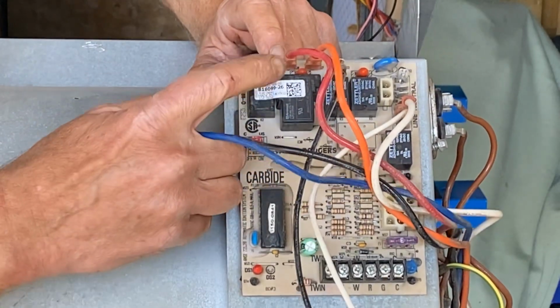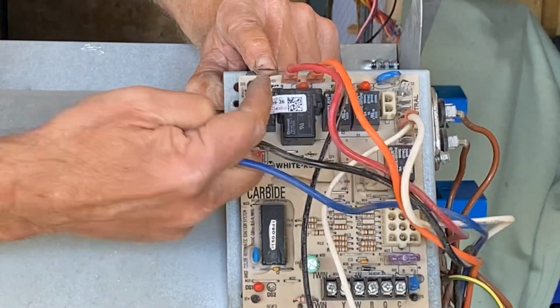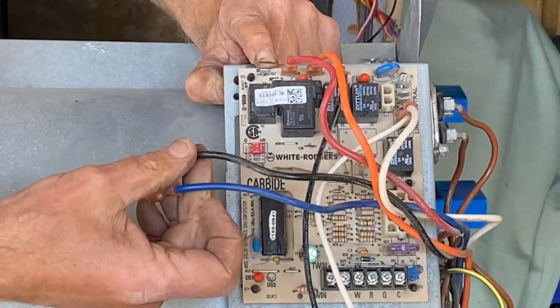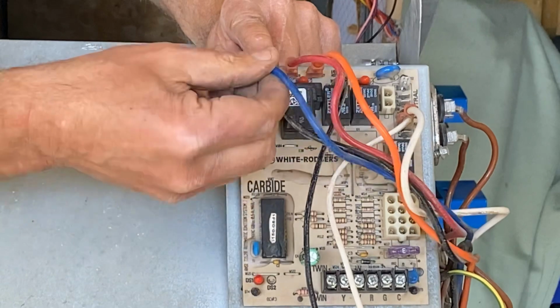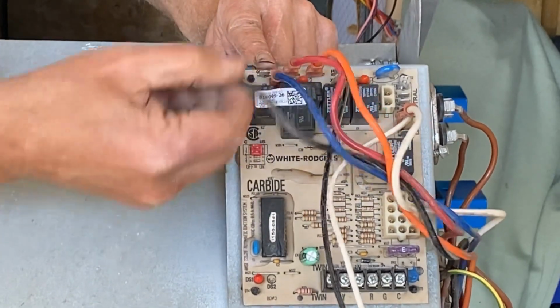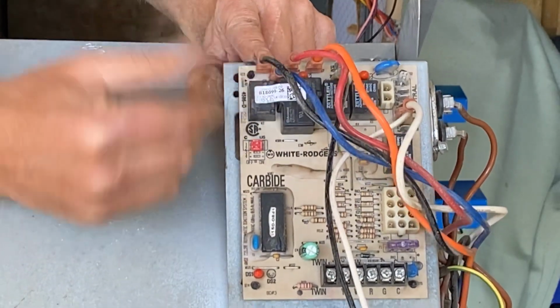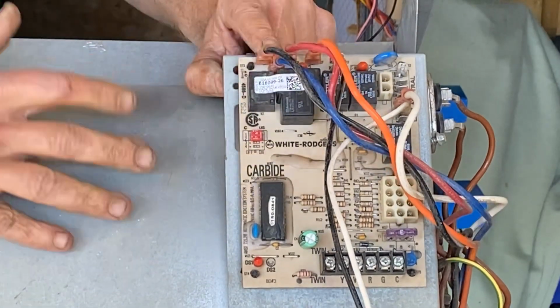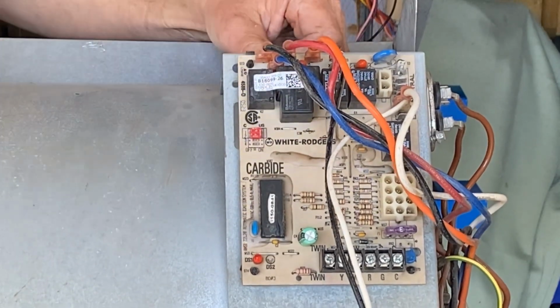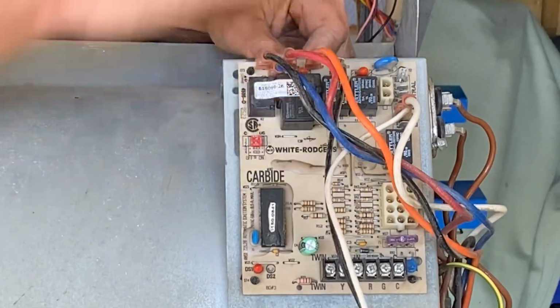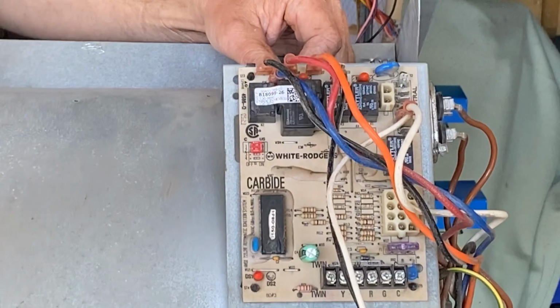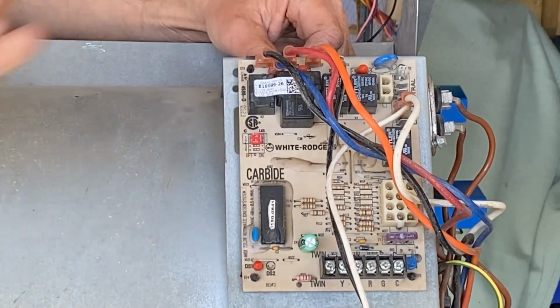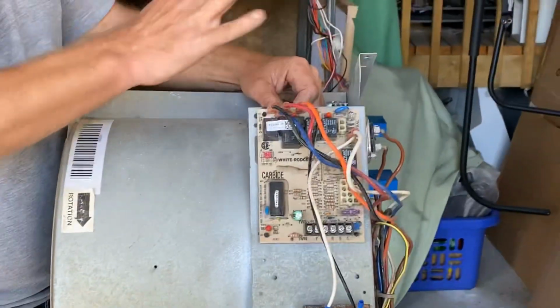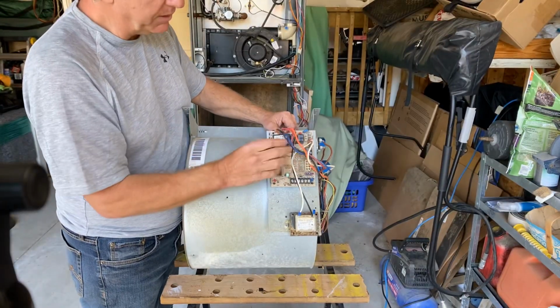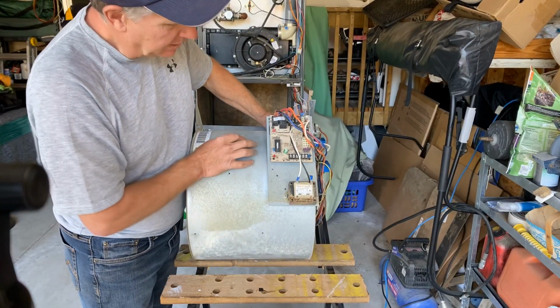Then I've got a terminal that says cool, and a terminal that says heat. I'm going to put the low speed on heat, and the high speed on cool. So now I've just set up my fan speeds where I want them. If I find those speeds don't meet the requirements I need, I can change this pretty easily from the blower - I don't have to take the blower out to do this, I can do it just with the door off, but you want to make sure the speeds are set properly.